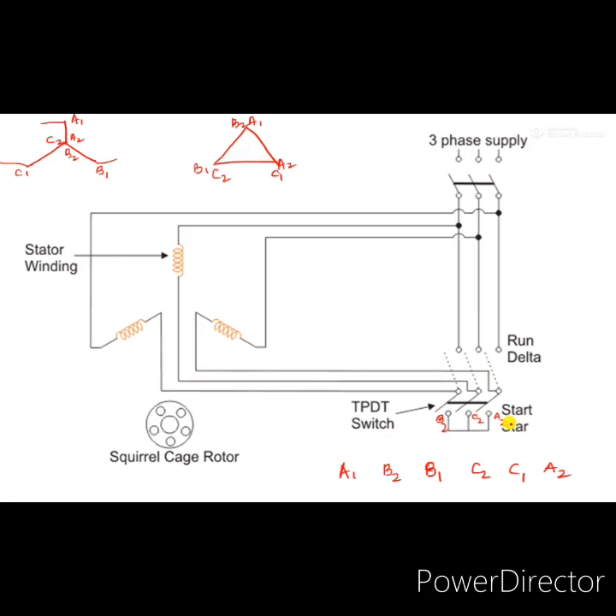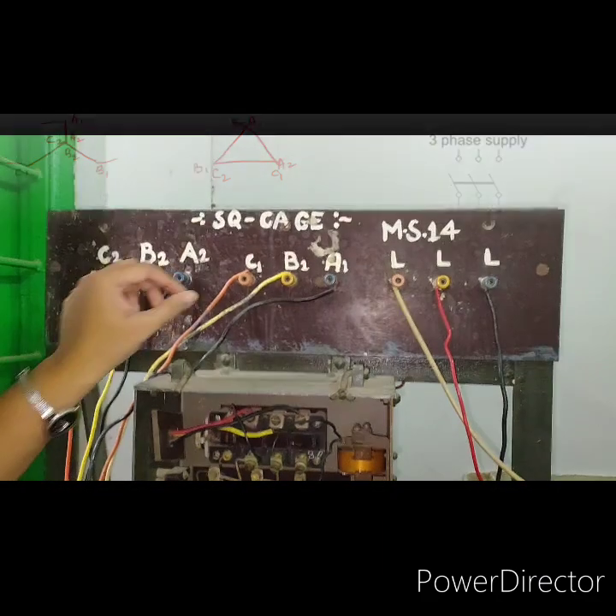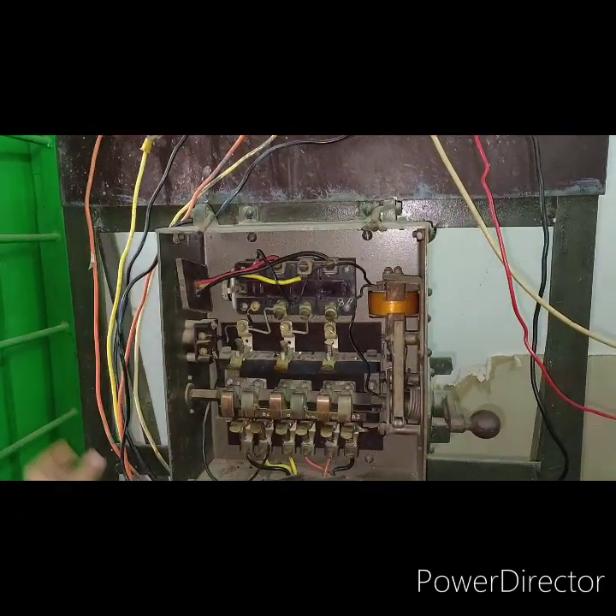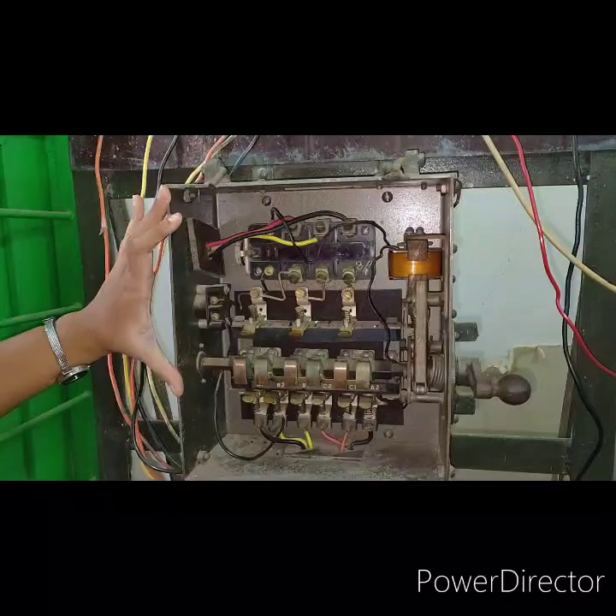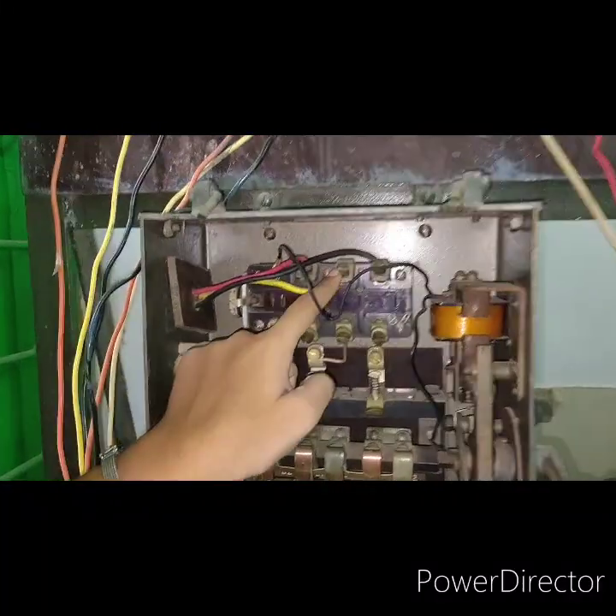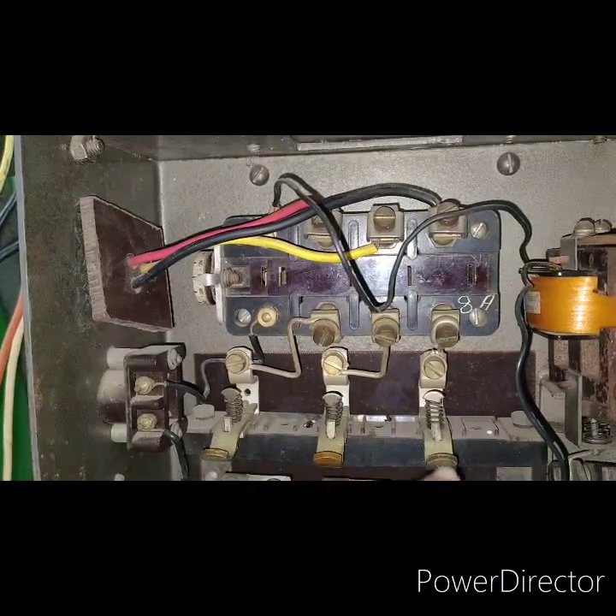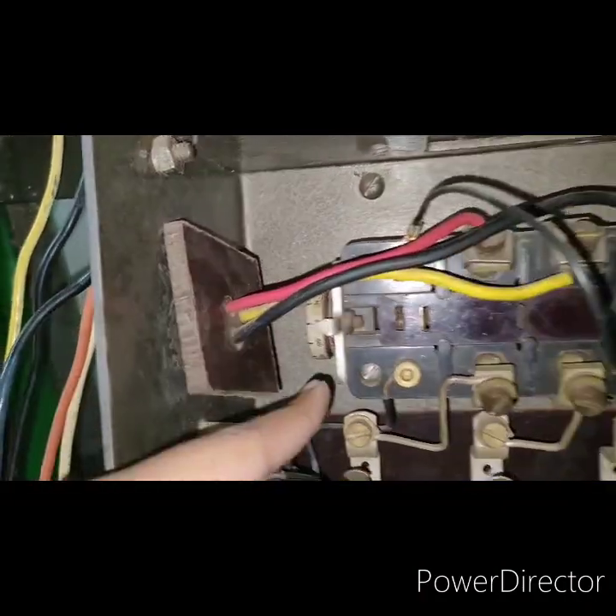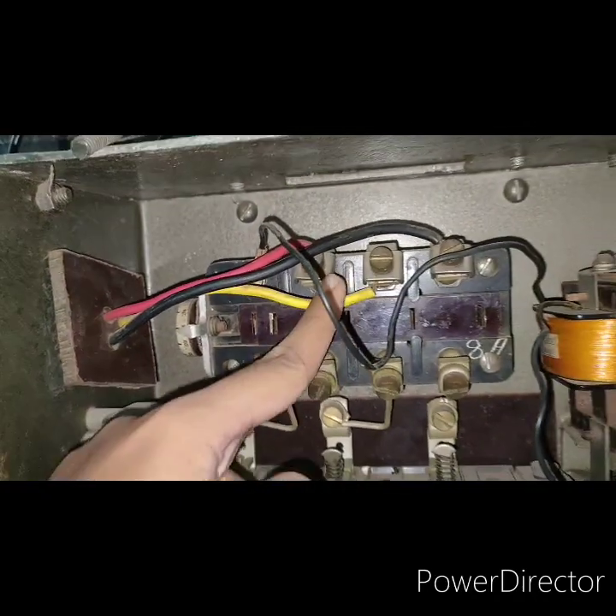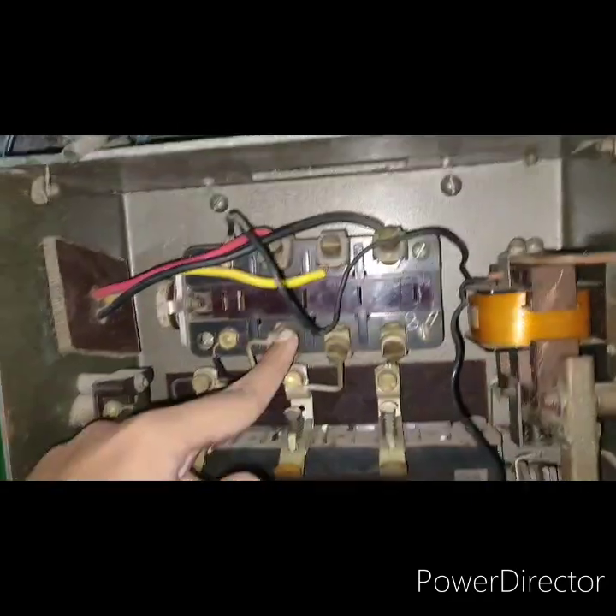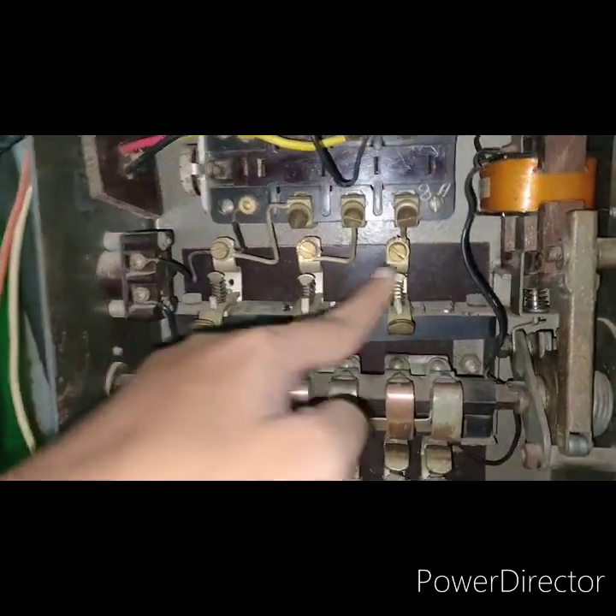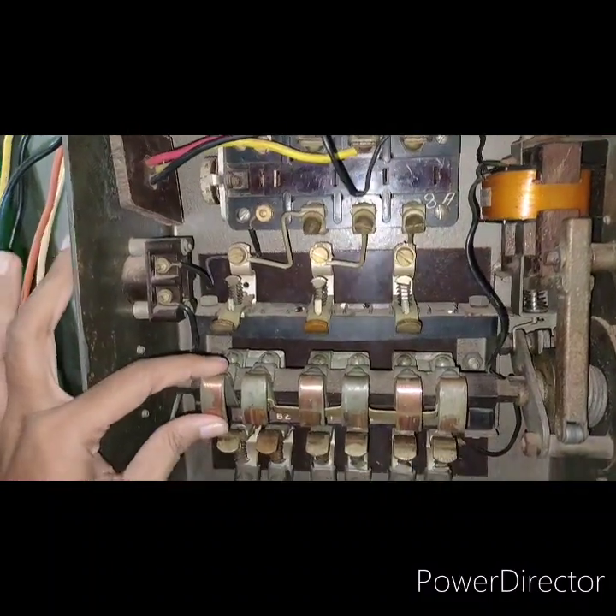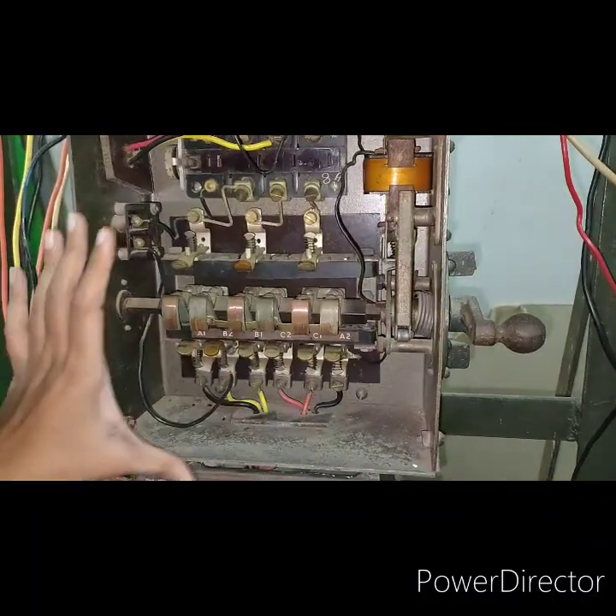The terminals A1, B1, C1, A2, B2, C2 are the terminals of the stator of the motor, and they are connected to the star-delta starter circuit. The supply terminals are connected to contactor switches through a relay — this is a current-time setting relay. Once the current goes above the set value, this relay trips and the supply gets disconnected from the contactor. These are the three contactor connections which are connected to the supply. This is the off position of the star-delta starter.